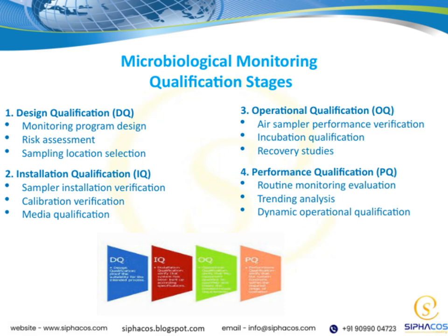Then, operational qualification verifies air sampler performance, incubation processes, and recovery studies. Finally, performance qualification evaluates routine monitoring, analyzes trends, and includes dynamic operational checks to confirm ongoing effectiveness. Each stage builds on the last to ensure reliable monitoring.